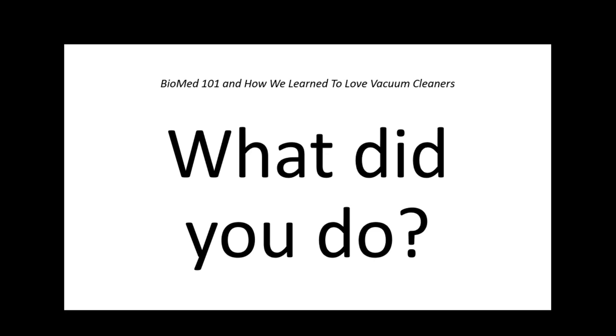So what do you guys do for possible COVID equipment when it comes back to your shop? Quarantine, yeah. Minimum of 2 weeks. So we have a quarantine area, a quarantine office, where you don't touch the stuff. We took one of the shops on the third floor, so it doesn't even leave that area. It just sits in there, and if we can, we bag it.